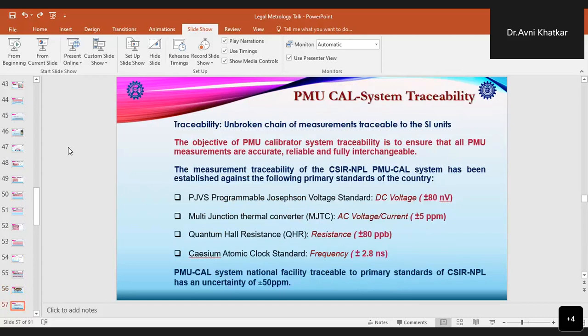And this PMU CAL system, as we are talking about its traceability, and as we all know, traceability is an unbroken chain of measurements which are traceable to the SI units. So the main objective of having traceability of the PMU calibrator system is to ensure that all the PMU measurements are accurate, reliable, and fully interchangeable. The measurement traceability of the CSIR NPL PMU CAL system is established against the primary standards of the country for the DC voltage. We have PJVS, that is, programmable Josephson voltage standard. For AC voltage and current, we have multi-junction thermal converters, that is, MJTCs. For resistance, the quantum Hall resistance standard is used, and for frequency, the cesium atomic clock standard is used. So the PMU-CAL system, the national facility, is traceable to the primary standards of CSIR NPL.